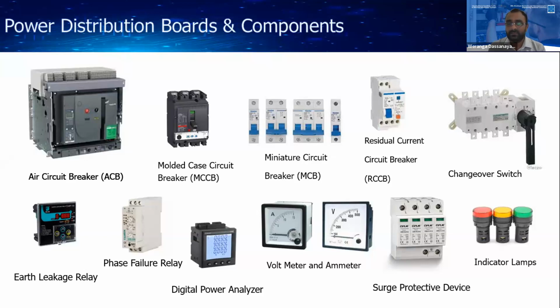Then you may all know this device, the circuit breaker, which we call a flip switch in your house. The next one is the changeover switch, which can be used instead of an automatic transfer switch to transfer the main power to a standby power, or from standby power to main power. Next one is the earth leakage relay, which detects the earth fault in the system and gives a tripping signal to the air circuit breaker or the molded case circuit breaker.